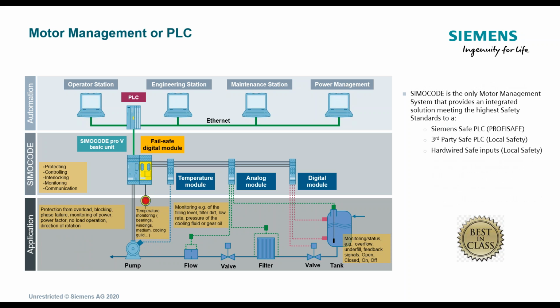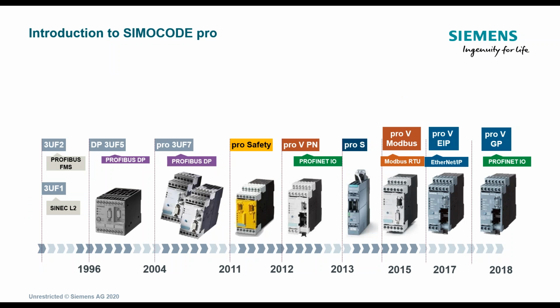Okay, then we add our safety. We could put an e-stop in here. Again, SIMOCODE can do PLC safety with PROFIsafe, or it can do it with a third party using a local safe module, and we can go up to SIL 3 or performance level e.